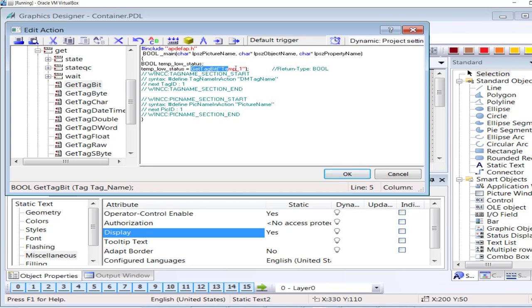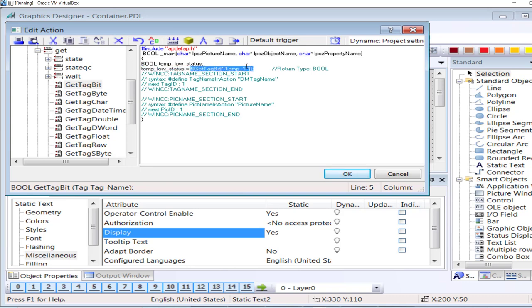I will be inverting the status. If Temp1 is low, I am going to assign this a high status. I will simply invert — put parenthesis and use the NOT operator. If Temp1 is high, GetTagBit Temp1 will return high and I invert the status. Then I will return 'TempLowStatus'. I will compile — zero errors and zero warnings.